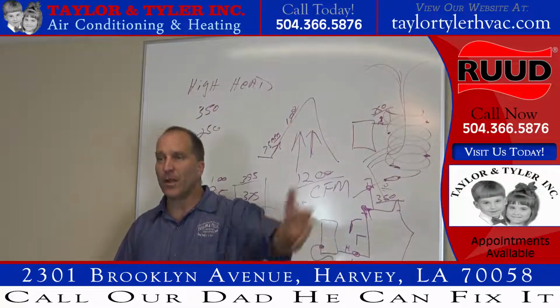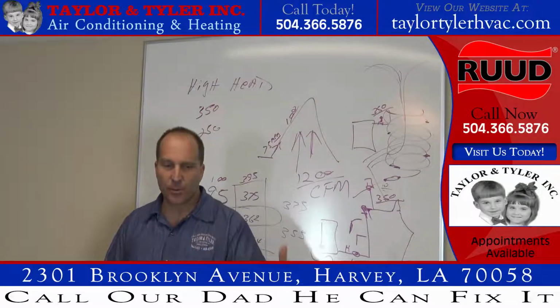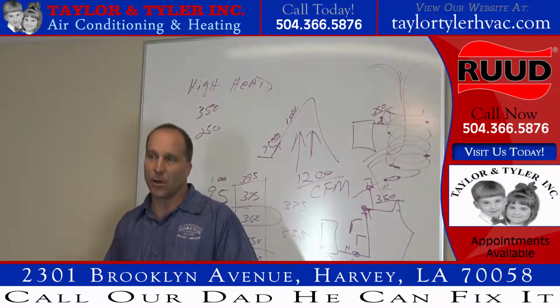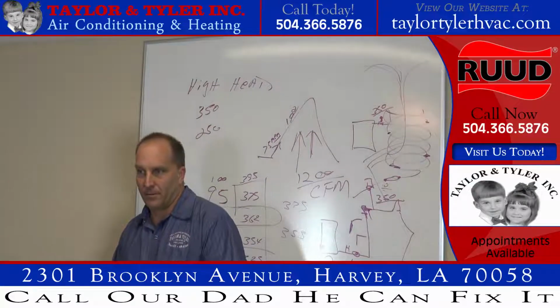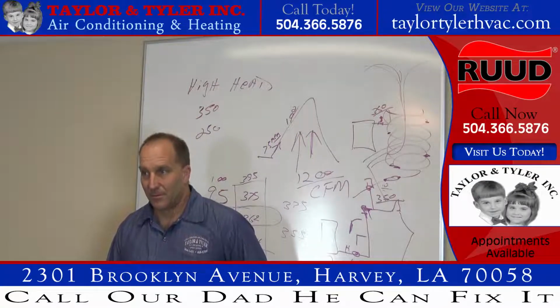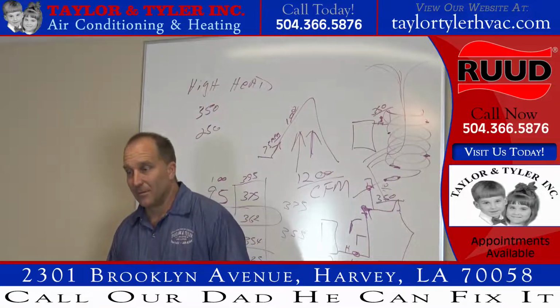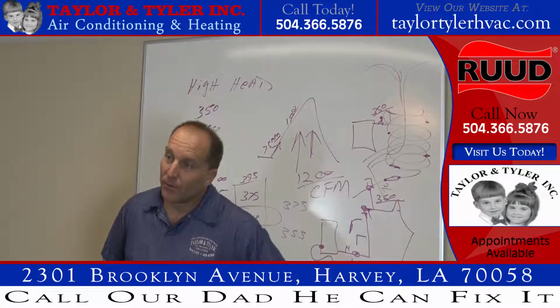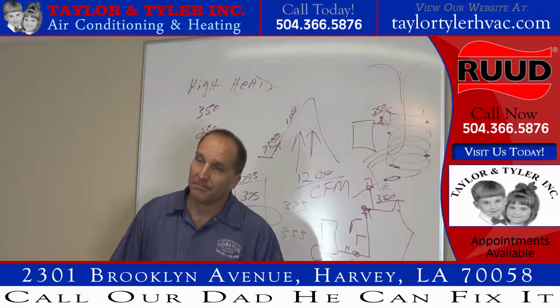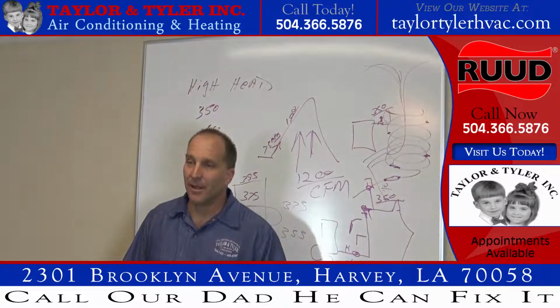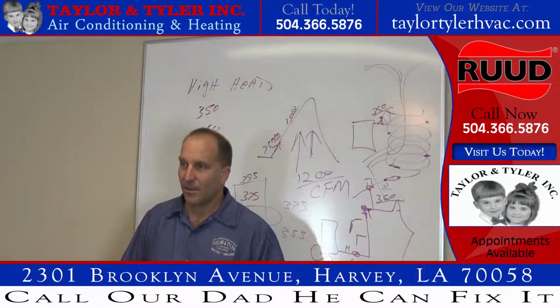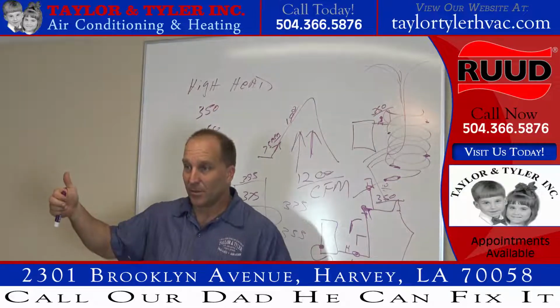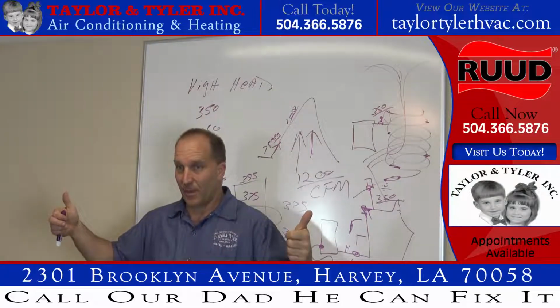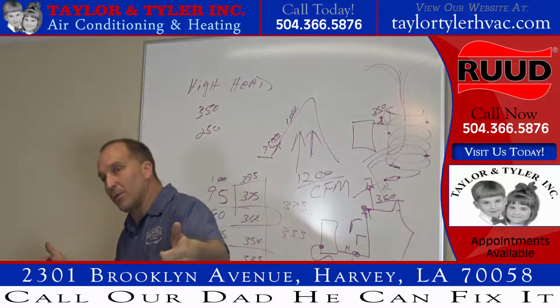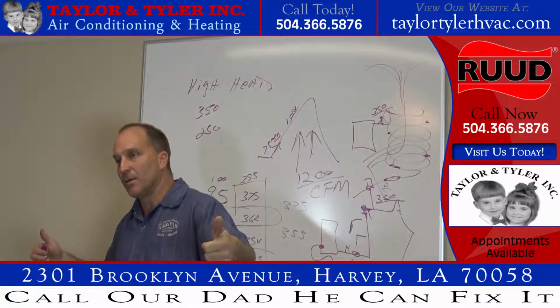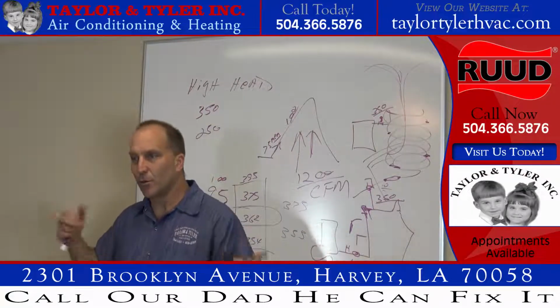But if my superheat's real high and my suction pressure is low, then is it overcharged or undercharged? 50 degrees. That's a low charge. Okay, so which one is it now? Is it overcharged or undercharged? In this case, it's perfectly charged. And it's giving me a high subcooling and a high superheat because it's restricting refrigerant through the system. So it's neither low on refrigerant nor too much refrigerant.